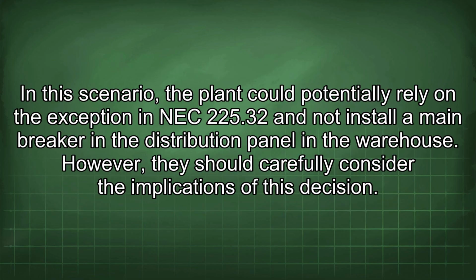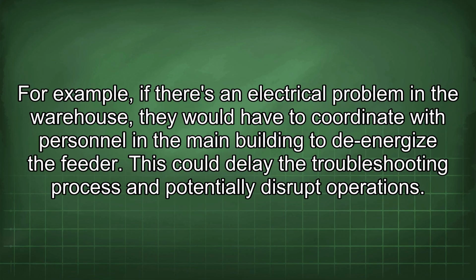In this scenario, the plant could potentially rely on the exception in NEC 225.32 and not install a main breaker in the distribution panel in the warehouse. However, they should carefully consider the implications of this decision. For example, if there's an electrical problem in the warehouse, they would have to coordinate with personnel in the main building to de-energize the feeder.